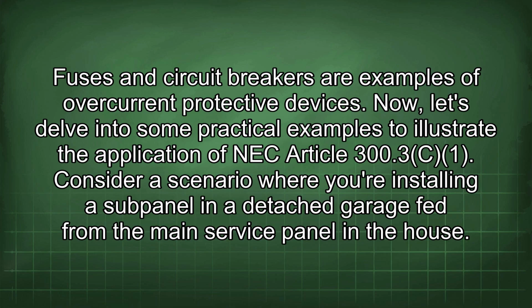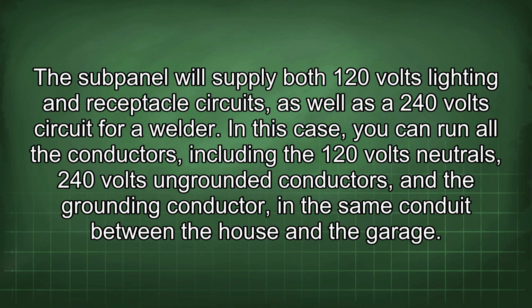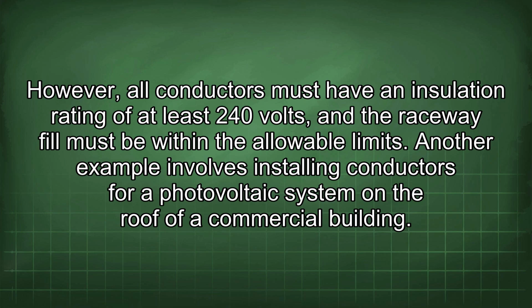Consider a scenario where you're installing a subpanel in a detached garage fed from the main service panel in a house. The subpanel will supply both 120 volt lighting and receptacle circuits, as well as a 240 volt circuit for a welder. In this case, you can run all the conductors, including the 120 volt neutrals, 240 volt ungrounded conductors, and the grounding conductor, in the same conduit between the house and the garage. However, all conductors must have an insulation rating of at least 240 volts, and the raceway fill must be within the allowable limits.